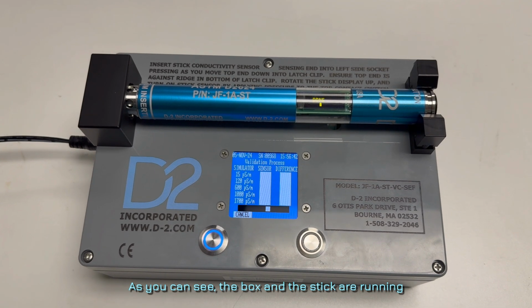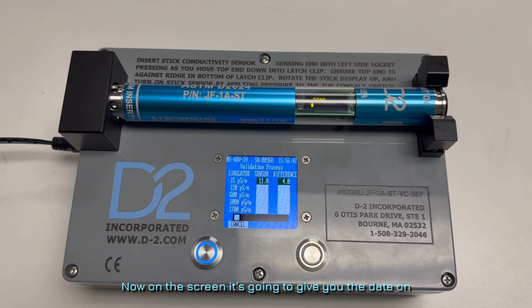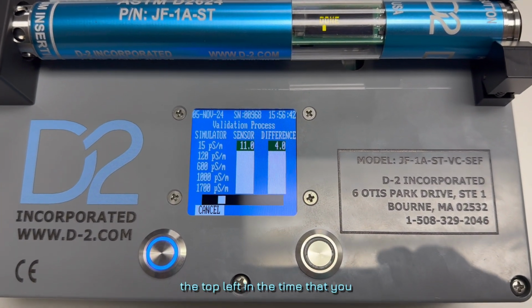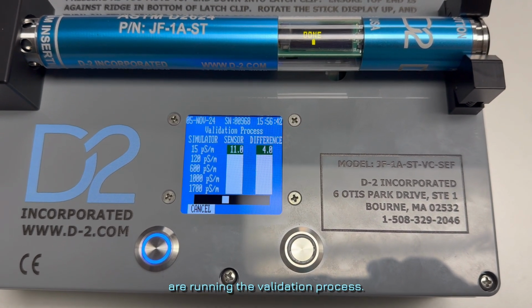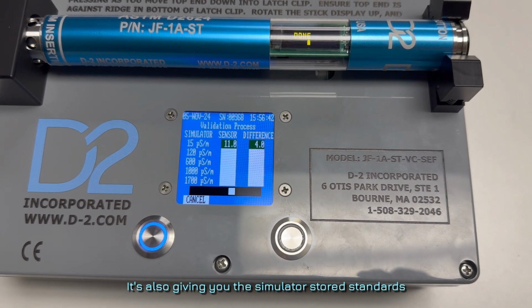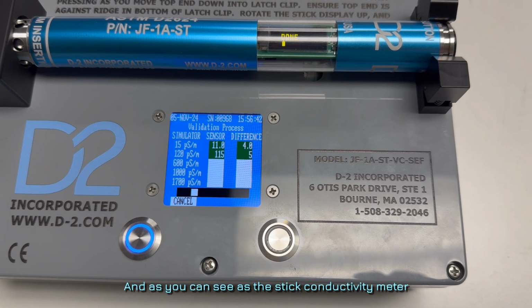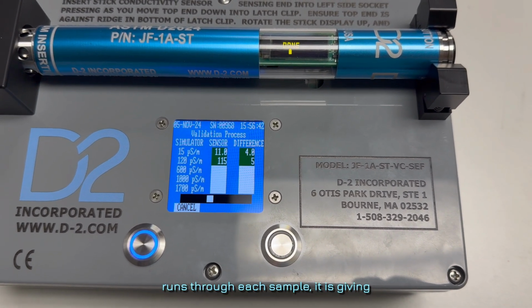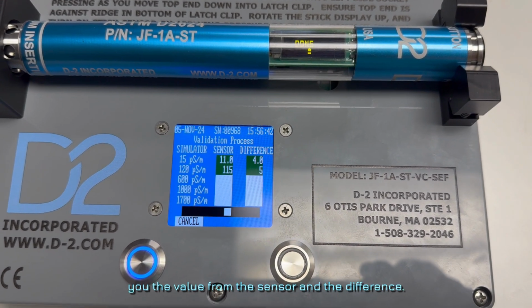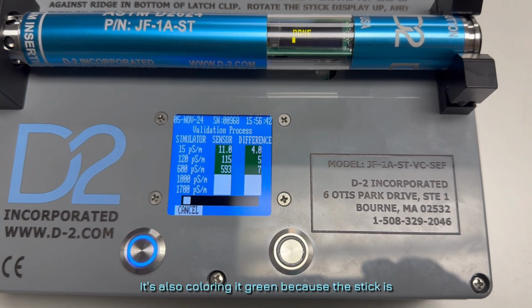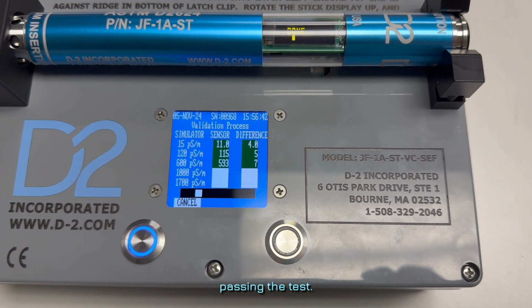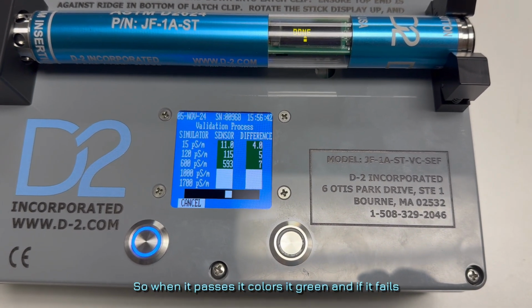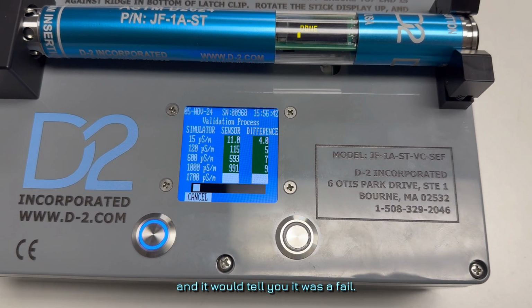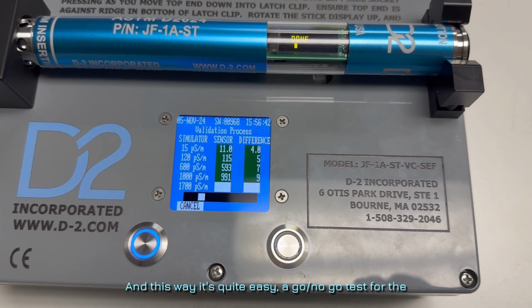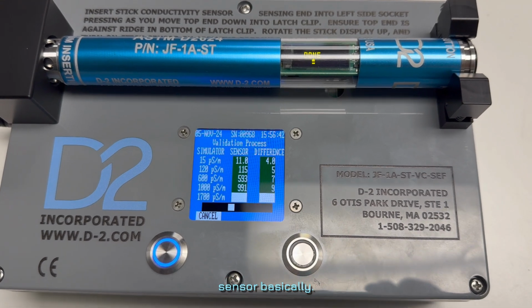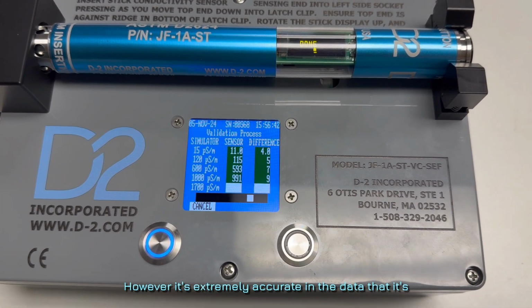So you can see the box and the stick are running through the process now. On the screen, it's going to give you the date on the top left and the time that you are running the validation process. It's also giving you the simulator stored standards on the far left in picosiemens per meter. And as you can see, as the stick conductivity meter runs through each sample, it is giving you the value from the sensor and the difference. It's also coloring it green because the stick is passing the test. So when it passes, it colors it green, and if it fails for a bad reading, it would be red and it would tell you it was a fail. And this way, it's quite easy, a go, no-go test for the sensor, basically. However, it's extremely accurate in the data that it's giving you.